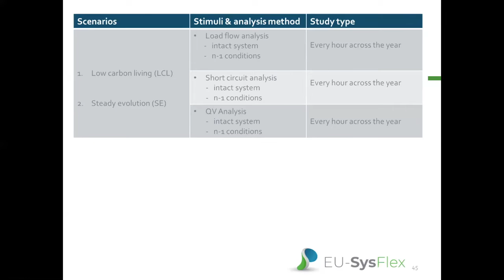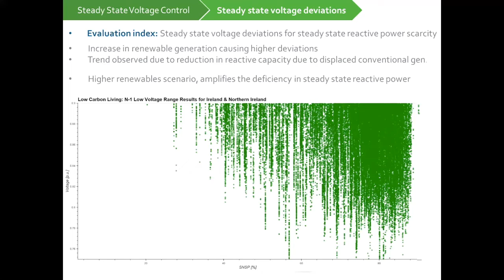For identifying the steady state reactive power scarcity, steady state voltage deviations have been used as an index. It can be seen in the figure below that as the penetration of renewable generation increases, represented by SNSP, the system non-synchronous penetration, essentially a measure of what percentage of the system load is being met by renewable generation, higher deviations of steady state voltage become apparent. This occurs due to the displacement of conventional generation by the renewable generation sources. For the scenario with higher renewable generation, which is the low carbon living scenario, there's a greater concentration of voltage deviations at high renewable penetration levels, indicating a higher steady state reactive power scarcity appearing in 2030 in the all island power system.